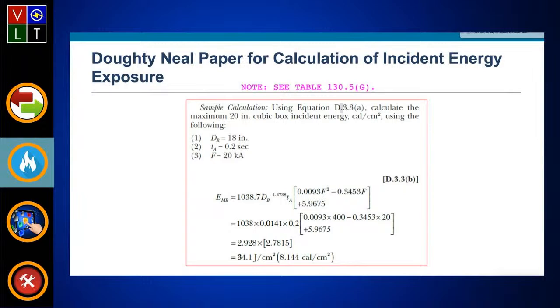And then, of course, this is the calculation. We go over to Annex D and look at D.3.3b, and run the calculation with the information given there. For this particular one, we come up with 8.1 cal, and we said yeah, we could use that 8.2 cal suit for that calculation. Remember looking at that earlier? Yep, and so that's running the calculation.